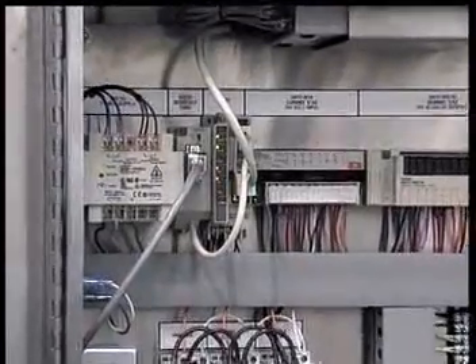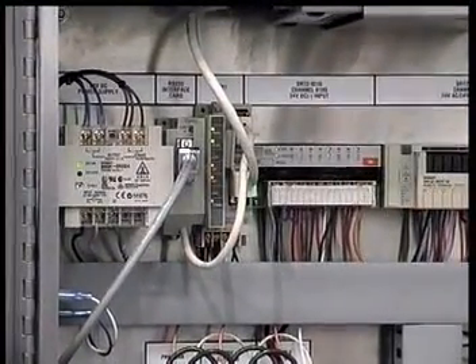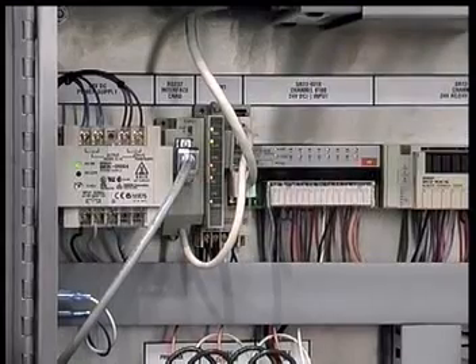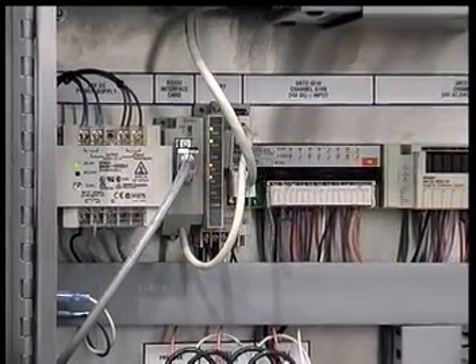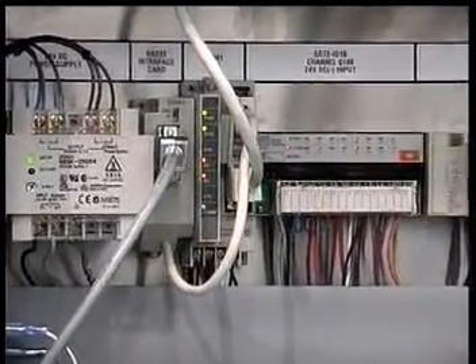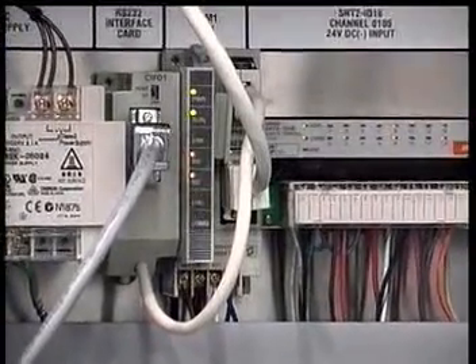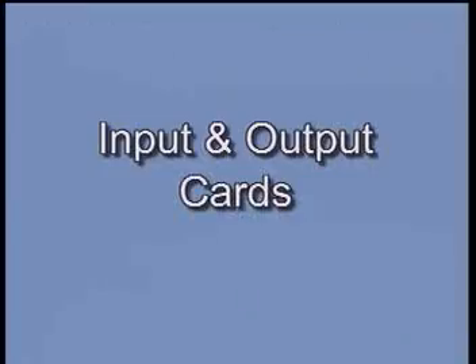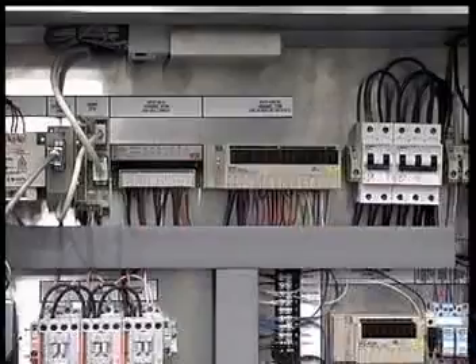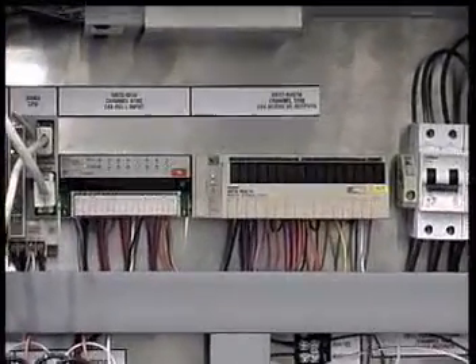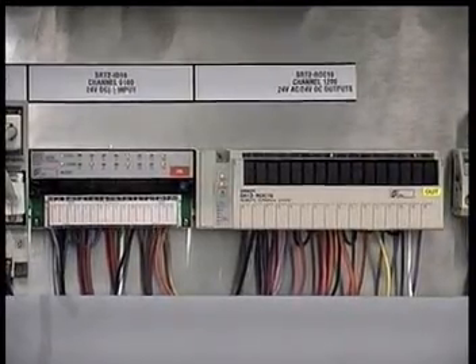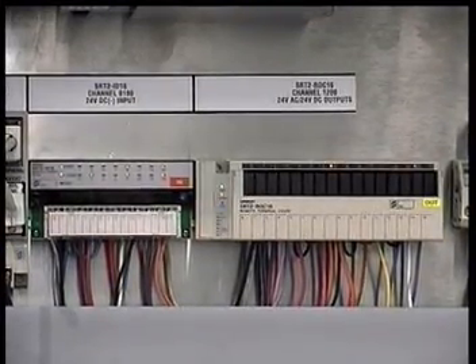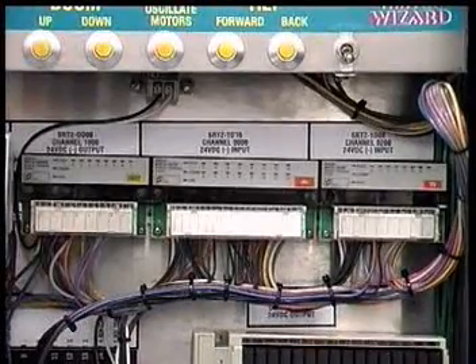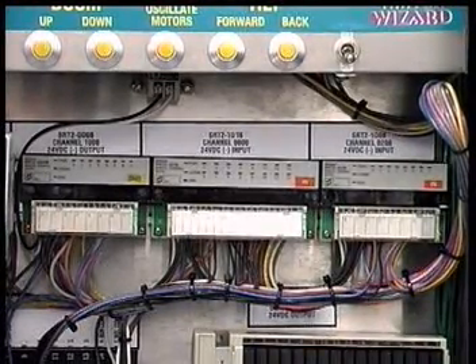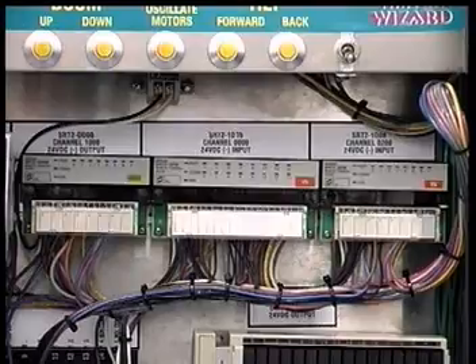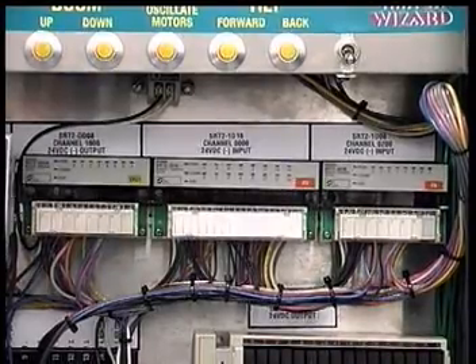The Water Wizard functions are controlled by a programmable controller, more commonly called the processor. In normal operation, the power and run lights will be on and a communications light will be flashing, indicating communication with the operator interface panel. The processor uses the input and output cards to control the electrical signals to and from Water Wizard components. In basic terms, input signals are sent into the processor by other components, and an output signal is the processor telling the components what to do.